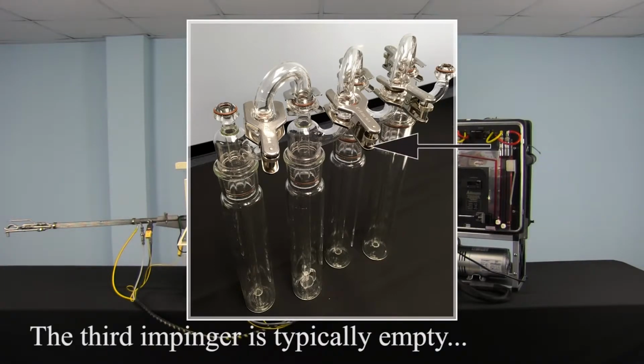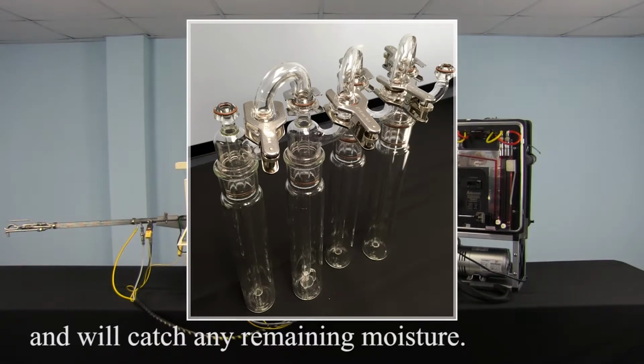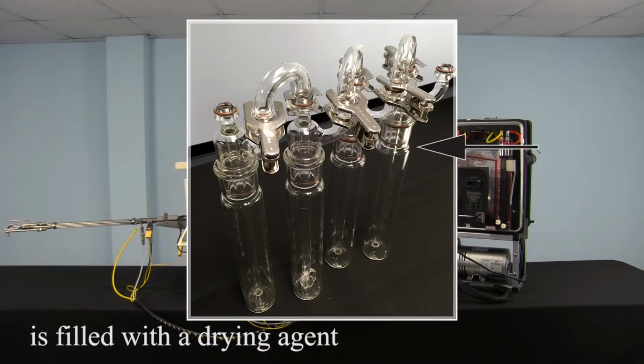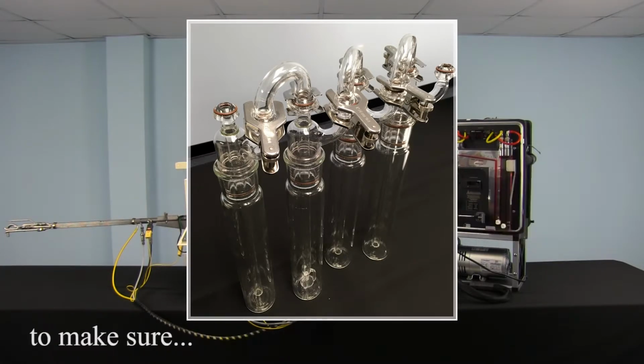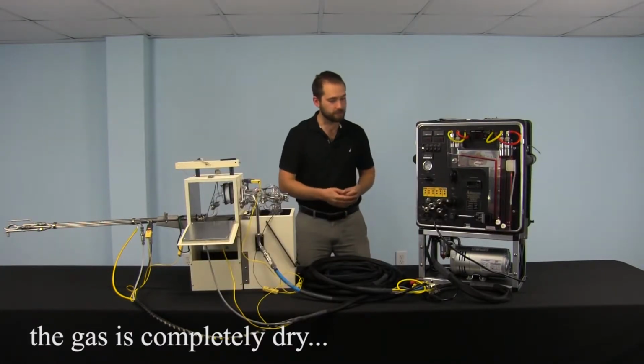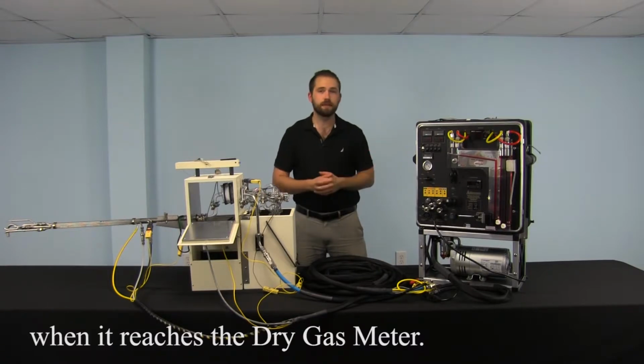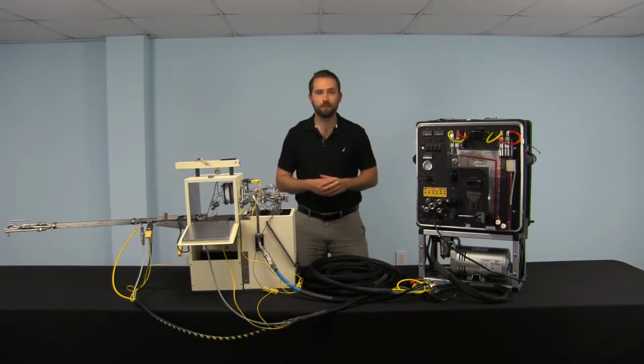The third impinger is typically empty, but if there's any remaining moisture, it will get trapped in the third impinger. And the fourth impinger is filled with a drying agent, silica gel, to make sure that as the gas passes through the system and ultimately ends up in the dry gas meter, that it's completely dry. We don't want to ruin the dry gas meter with wet gas.